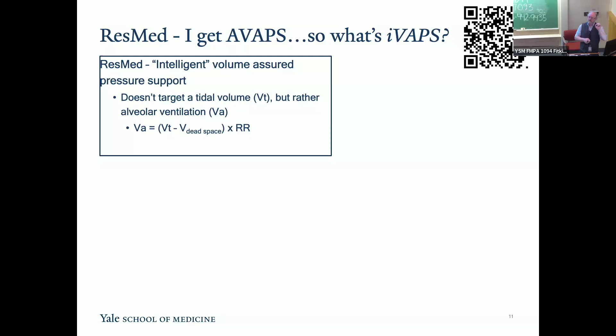So iVAPS doesn't target the tidal volume, it targets alveolar ventilation. And so it's making a calculation: you enter in the patient's ideal body weight and height, and it figures out what the anatomic dead space is. And so for each breath, we take tidal volume minus anatomic dead space, and that's the alveolar breath. You multiply that by the respiratory rate, and that's alveolar ventilation per minute. So the device is targeting alveolar ventilation per minute. For each breath, total tidal volume minus the dead space.